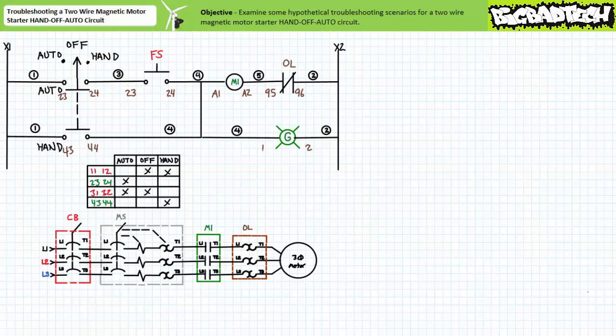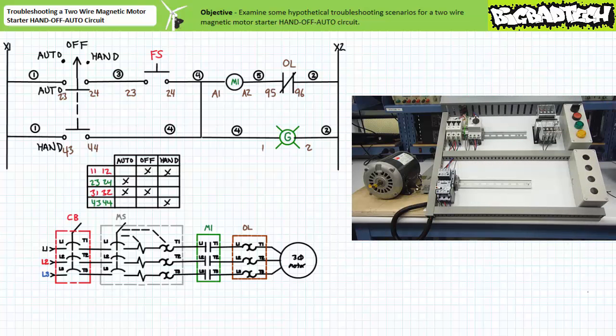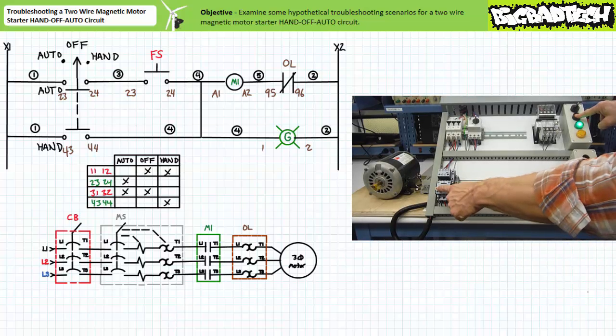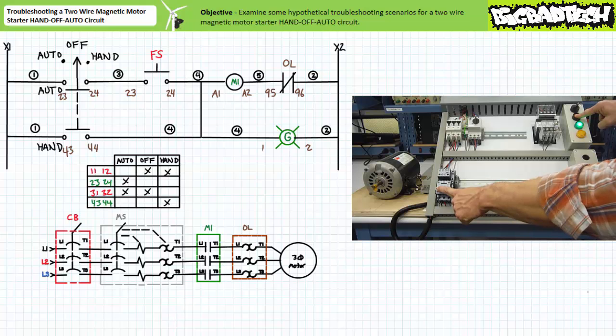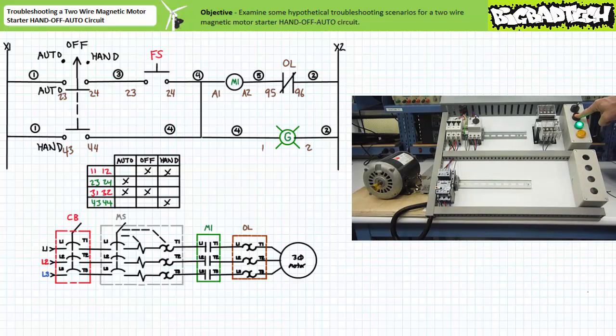Additionally, consider this circuit's response to an overload event caused by a large mechanical load, a locked rotor, or a single phasing event. Consider what would happen if the overload relay was in the automatic reset mode. In this case, I'm simulating an overload event by pushing in the manual test button. The triggered overload element signals the contactor to open as expected. When the overload element in automatic mode cools, it automatically resets. If the simulated float switch is still being triggered, the motor springs to life unexpectedly.